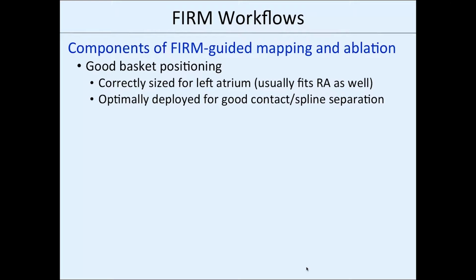They tend to separate out pretty nicely on their own, but sometimes, especially if it's a relatively tight fit, you have to give a little bit of a twist on it and move the catheter in and out to get the splines to separate nicely and make good contact.